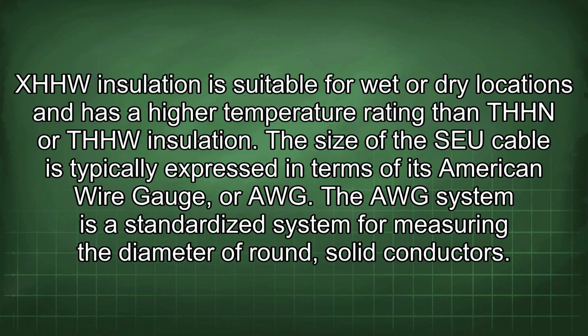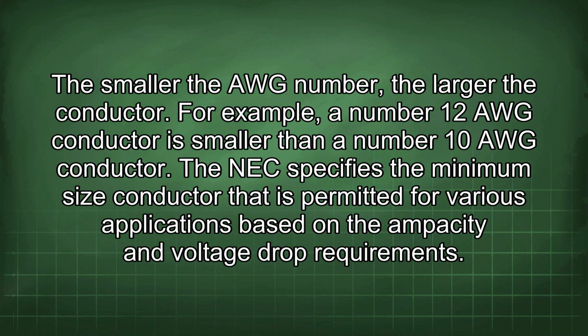The size of the SEU cable is typically expressed in terms of its American Wire Gauge, or AWG. The AWG system is a standardized system for measuring the diameter of round, solid conductors. The smaller the AWG number, the larger the conductor. For example, a number 12 AWG conductor is smaller than a number 10 AWG conductor.